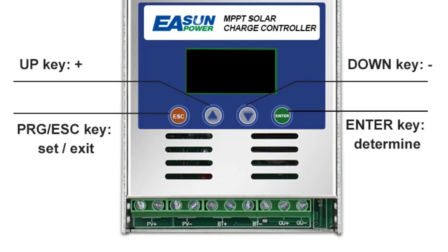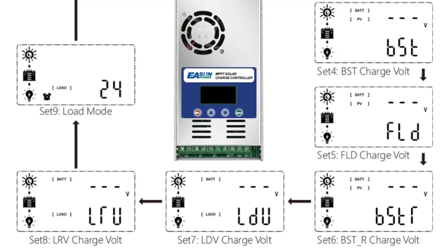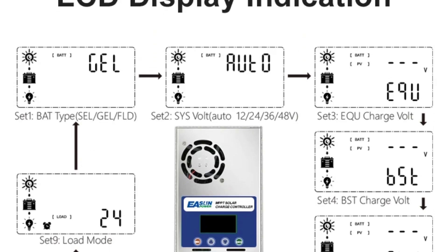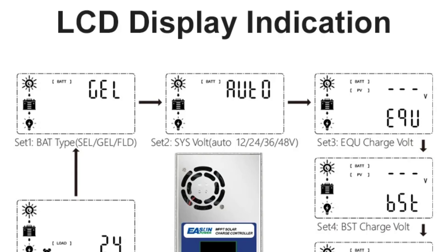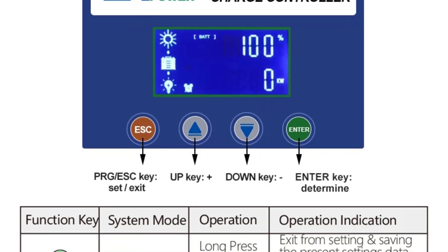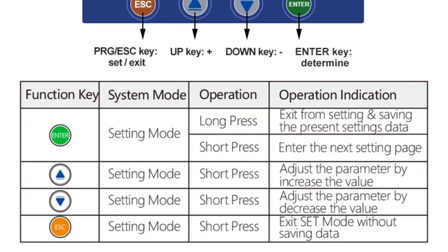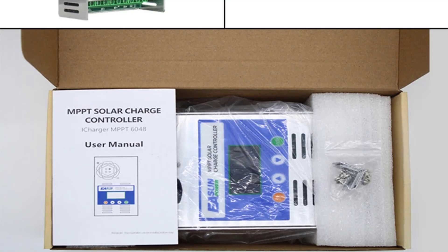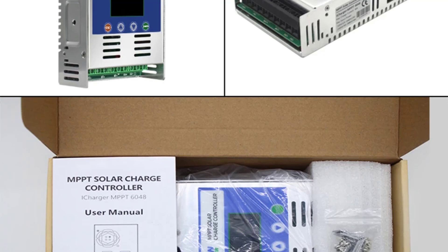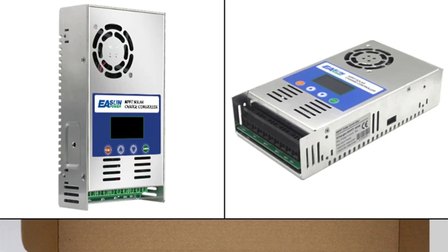With a high PV utilization rate of 99%, the EASUN Power controller maximizes the energy harvested from solar panels, improving the overall efficiency of your solar system. The controller supports large solar arrays, with a maximum input power of 2,880W for 48V systems, making it suitable for more demanding installations. The temperature-controlled fan cooling system adds to the longevity and reliability of the device — the fan automatically turns on when the temperature exceeds 45°C and turns off when it drops below 40°C, ensuring optimal performance even in warmer environments. The controller also features a robust enclosure with an IP21 rating, which protects against dust and light moisture exposure, making it suitable for indoor or sheltered outdoor setups.